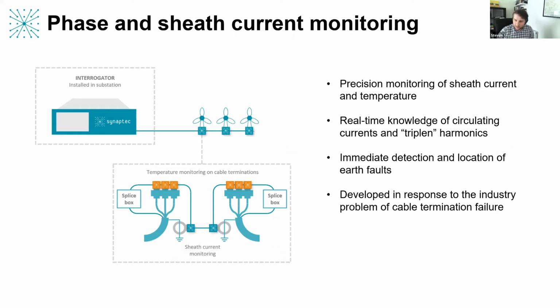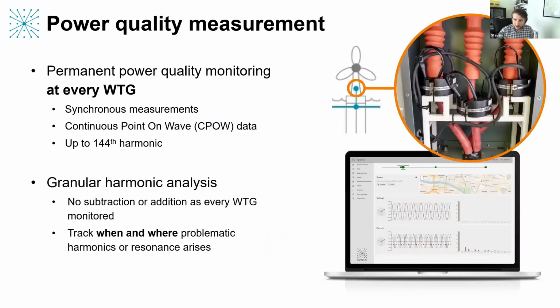Another thing we can do with sheath monitoring is look at gradual increases in the sheath currents over time. If we look at it for long enough, we can distinguish between natural variations in the sheath current due to different wind output, but we can detect subtle increases which may indicate certain failure modes in the cable. So that's the first application I wanted to mention, which is related to power quality. But now focusing more on what's more conventionally known as power quality.